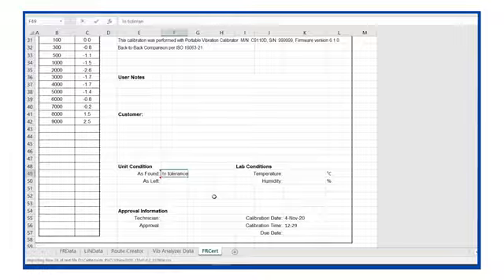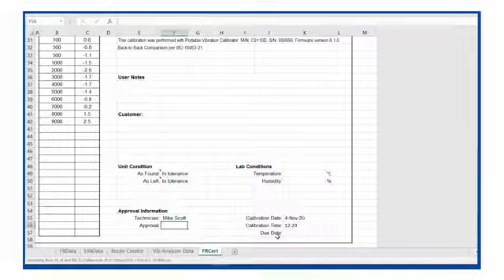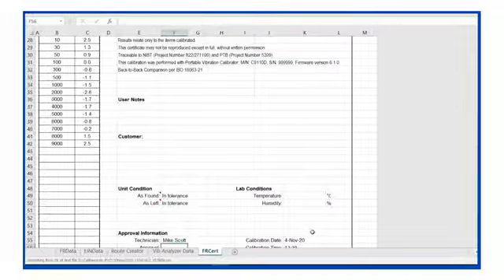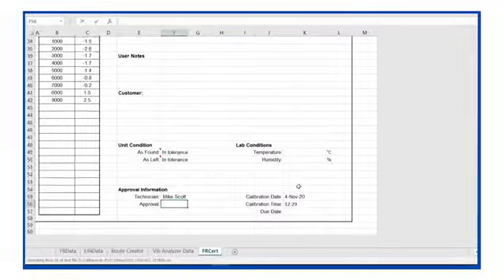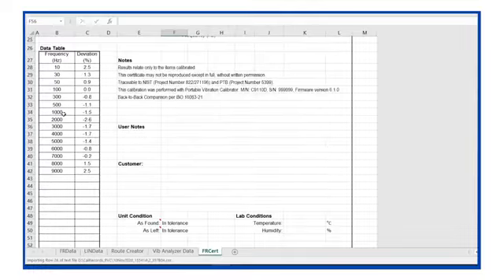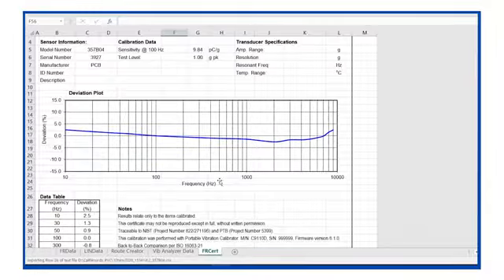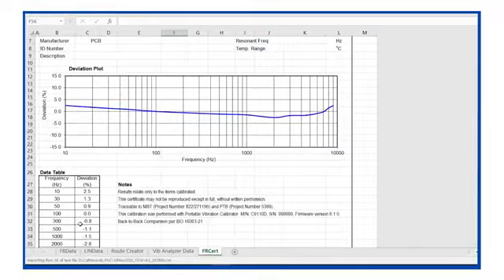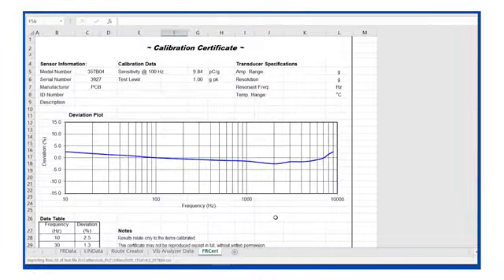As found and as left are both in tolerance. So I'm not going to adjust anything here. And I can put myself down as a technician. The date and time shows up here on the bottom right. You cannot change the date and time. That's what makes it an ISO 17025 compliant document. You also cannot change any of the raw data here in the data table. So if you accidentally click somewhere, there's no way to manipulate your data by accident. And that's the calibration certificate for the 357B04.